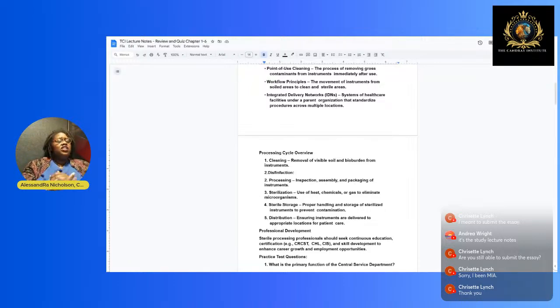You're never going to guess. You're never going to say, well, Alessandra told me when I was in class that you always do this, this, and this. No, she said you always check your instructions for use, okay? So you're going to do that sterilization method, whether it uses chemicals like hydrogen peroxide, ETO, plasma, whatever it may be. You're going to use that chemical, that gas, and that heat to eliminate the trace of any leftover microorganisms that may cause infection. You're going to kill them all, right? That's your job. You're a warrior.